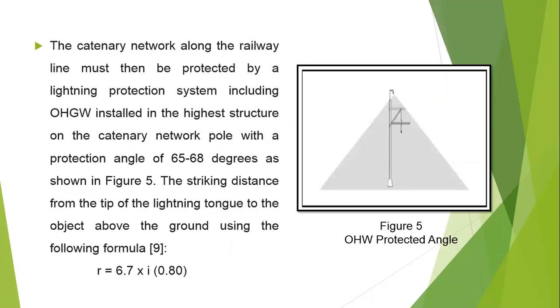The catenary network along the railway line must be protected by a lightning protection system, including OHGW installed in the highest structure on the catenary network pole with a protection angle of 65 to 68 degrees, as shown in figure 5. The striking distance from the tip of the lightning rod to the object above the ground uses the following formula: R equals 6.7 multiplied by I multiplied by 0.8.